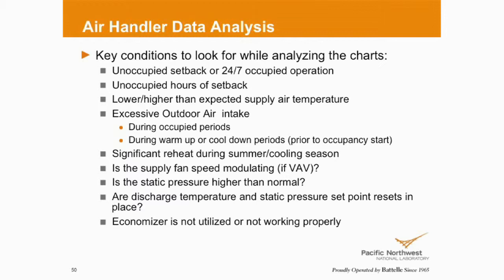If it's hot and humid like we're going to have here, and I'm bringing in 10, 20% of that air, I'm challenging my mechanical cooling system right out the gate. If it was cold like you had this winter, I'm challenging my heating system right out the gate. I don't need to. No one's in the building. I don't need to ventilate.